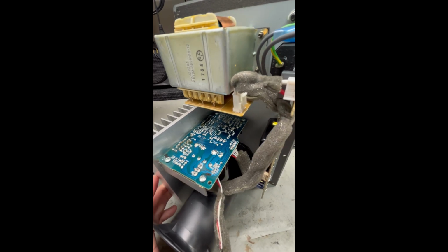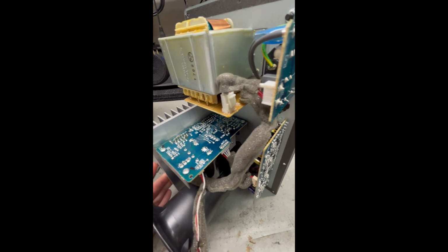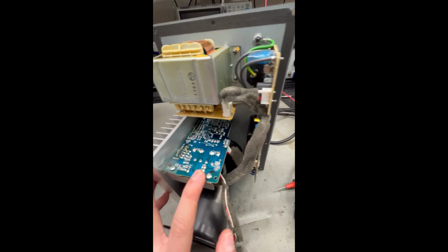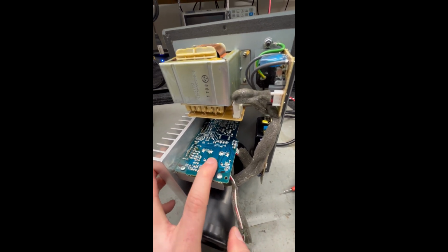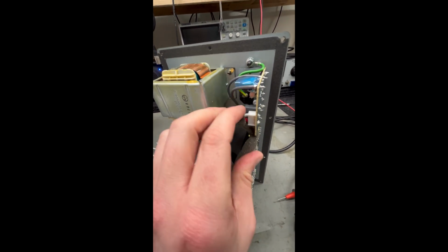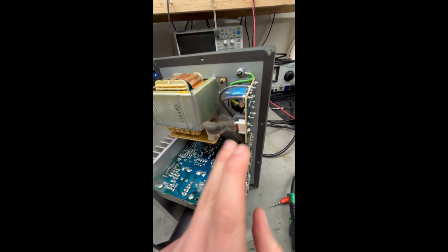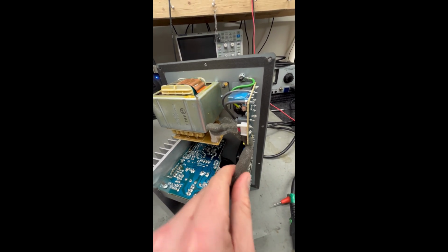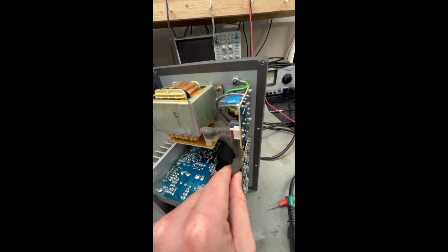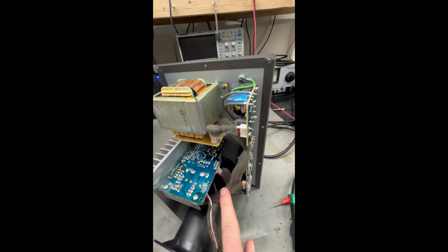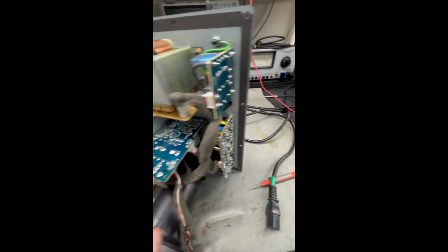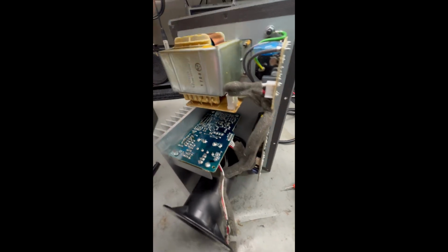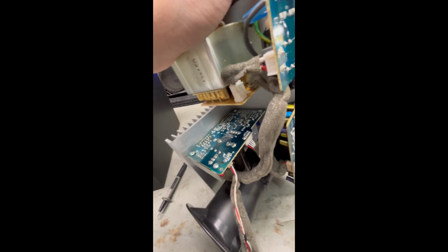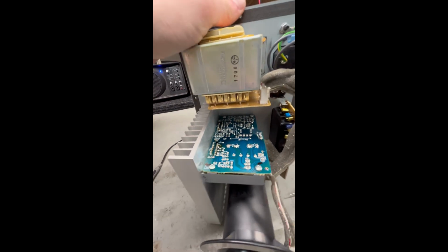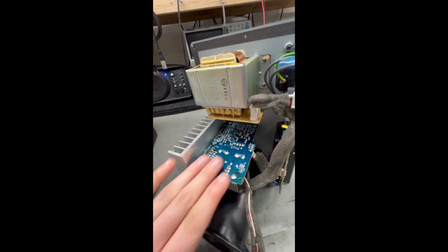So what we can do is check the AC that is on these pins here, coming from the transformer itself, not the input board. We're going to check for alternating current here, because this is where that cable is connected, to make sure that we actually have AC moving into this power board.